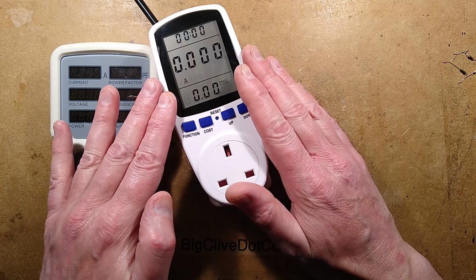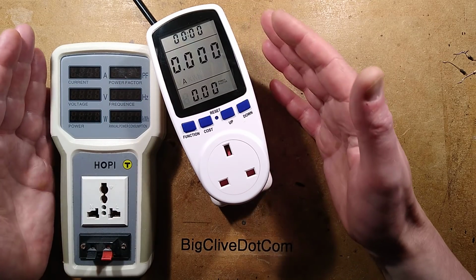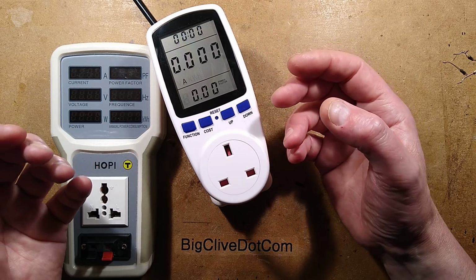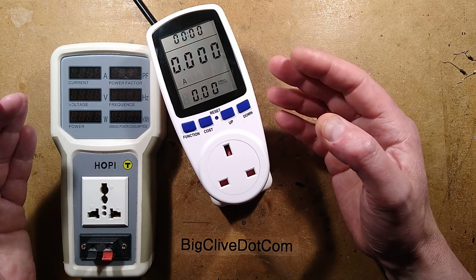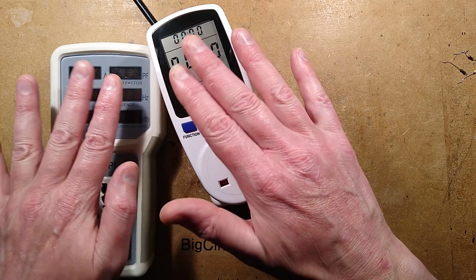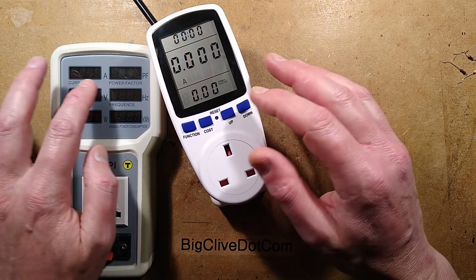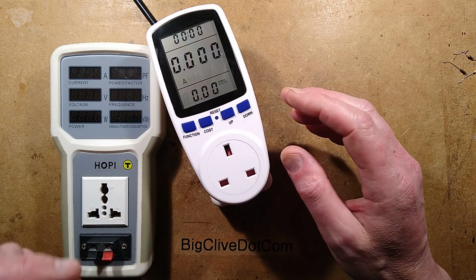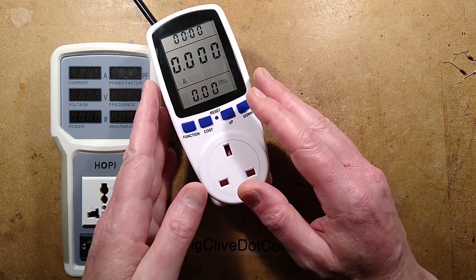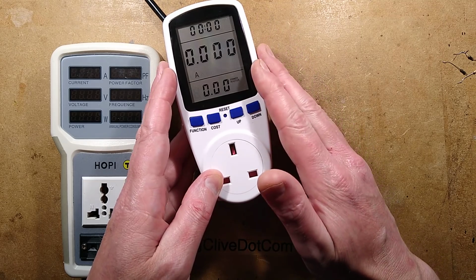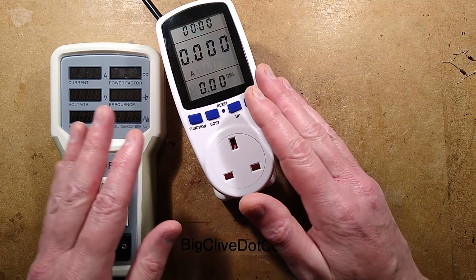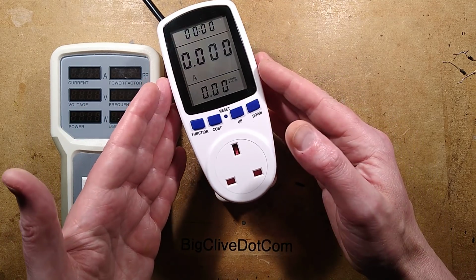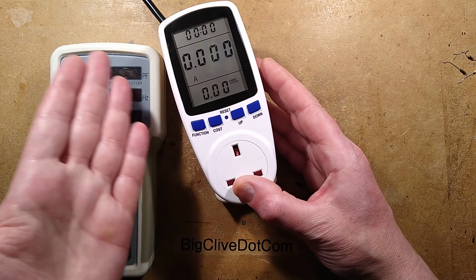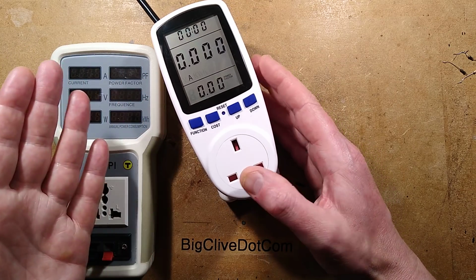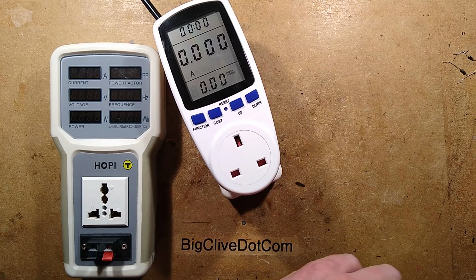However, the accuracy is really surprising. I tested this at various loads. I tested it with a 1/2 watt LED lamp, which is quite an awkward load, and they were pretty much identical. There's a slight decimal point difference between them, but that's it. As the power went up to 100 watts, this one drifted by about 1 watt, and I used the Fluke to test the voltage reading, and at 240 volts it was only 1 volt off, so it's actually really surprisingly good.